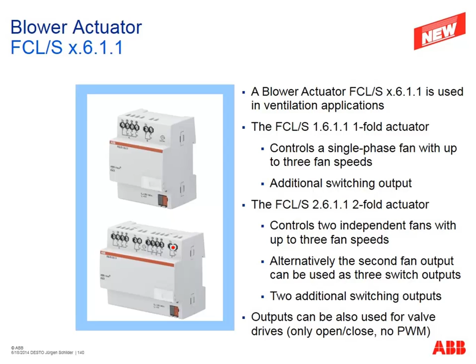So the next device is the FCL/S 2.6.1.1. The 2 means we can control 2 independent fans. Here the fan number 1 and here the absolutely independent fan number 2. Additionally, we have 2 switching outputs like before, to switch the light, for example, or to switch on a main switch in our fan. It is also possible to use these 2 switch outputs, for example, to control valve drives, but only in an easy way. We can open or close the valve drives, but we have no parameters like we needed for pulse width modulation. So basically it is possible to control valves, but only in an easy way.